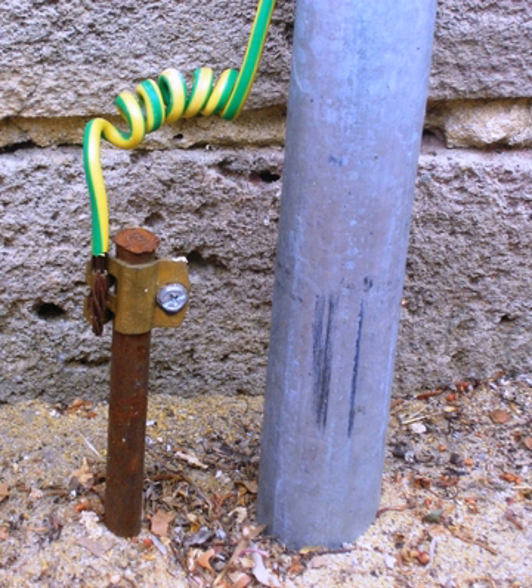Equipment bonding conductors provide a low impedance path between normally non-current carrying metallic parts of equipment and one of the conductors of that electrical system's source. If any exposed metal part should become energized by a fault, such as a frayed or damaged conductor, it creates a short circuit, causing the overcurrent protection device, circuit breaker or fuse, to open, clearing, disconnecting the fault. It is important to note this action occurs regardless of whether there is a connection to the physical ground, earth. The earth itself has no role in this fault clearing process since current must return to its source. However, the sources are very frequently connected to the physical ground, earth.